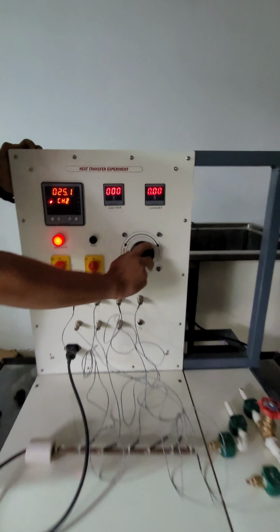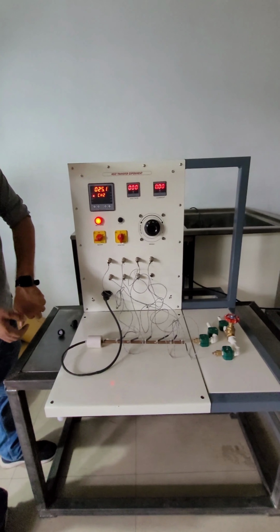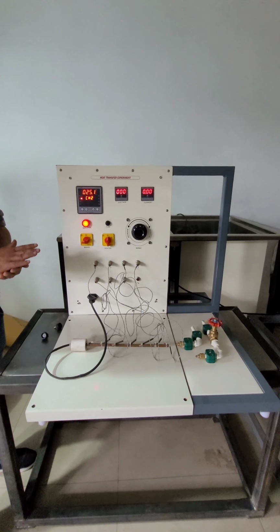to the requirement. Also, you have to note that whenever you are giving the heat input, you have to refer to the manual for the maximum heat input or maximum temperature limitations given for that particular accessory, and you have to take care not to exceed that limit so that the fittings are not damaged. As you can see, we have used heaters of different capacities, and each heater has a limited capacity. So we must not go over that value, and those values we can find in the instruction manual.